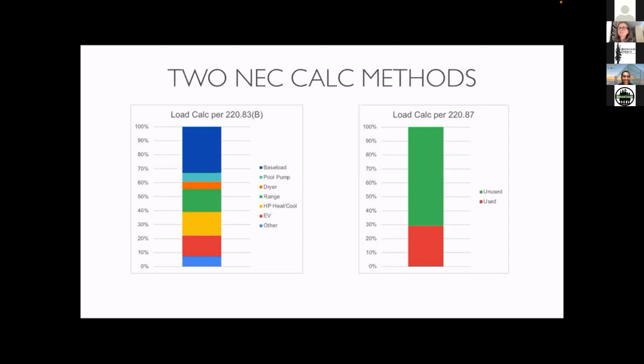Over on the right, using 220.87, I still have a lot of headroom. How does 220.87 work? It looks at historical electric loads from your utility bill, taking either 15-minute or 1-hour increments, looking at energy usage over that period. We assume that roughly reflects what the maximum power would be over that period, and that enables us to figure out, over a 12-month period, what was the maximum of your panel that you used.